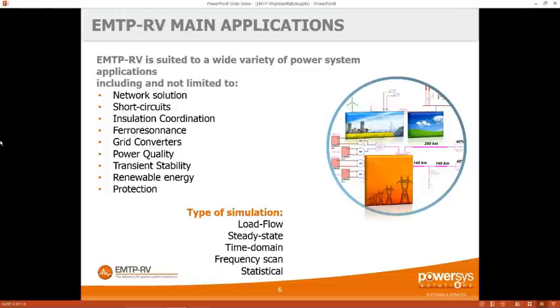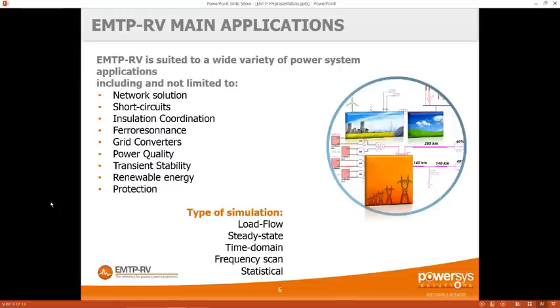Ferroresonance can be studied as well. A lot of customers use EMTP for ferresonance, where you can change initial conditions like the flux in the transformer. For grid converters and renewable energy with power electronics, we study every single switching cell with the saturation in the IGBT, the control, and the protection — a very large but extremely precise model. For all renewable energy and power electronics, the transient software approach is the most valid.